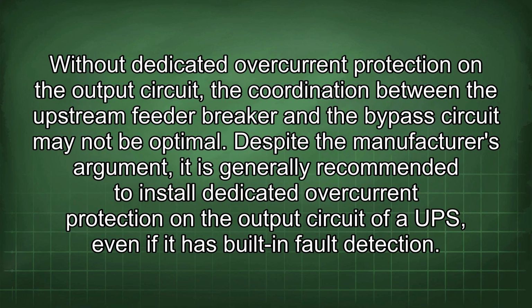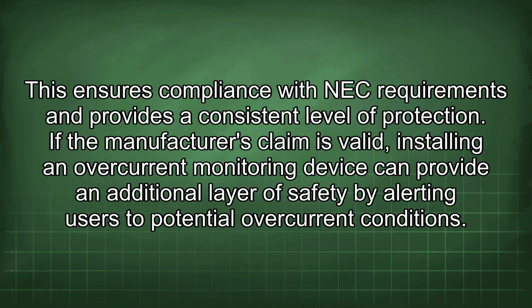Without dedicated overcurrent protection on the output circuit, the coordination between the upstream feeder breaker and the bypass circuit may not be optimal. Despite the manufacturer's argument, it is generally recommended to install dedicated overcurrent protection on the output circuit of a UPS, even if it has built-in fault detection. This ensures compliance with NEC requirements and provides a consistent level of protection. If the manufacturer's claim is valid, installing an overcurrent monitoring device can provide an additional layer of safety by alerting users to potential overcurrent conditions.